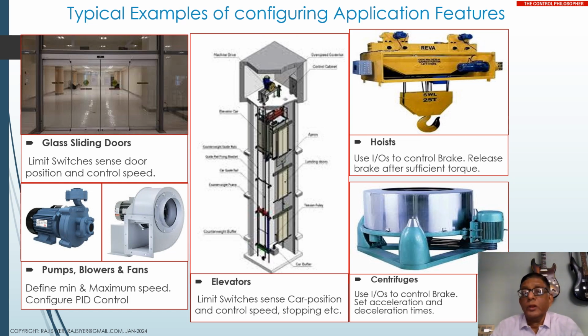Right? Okay, next, we take the example of hoists. As I told you, hoists such as these have a brake. The brake engages the drum on which the wire rope is wound, so that under heavy loads the winch doesn't slip away. So these brakes are released not when the motor starts. They will be released when the drive has developed enough torque.